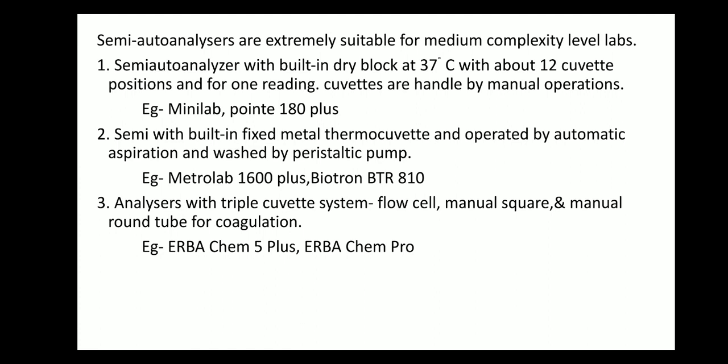So the aspiration, after the reagent and sample is mixed, once the reaction is over, to give out the reading, this mixture has to be aspirated, right? So that aspiration is automatic in this type. And washing is the washing of the flow pump and the cuvettes, which have to be rinsed and washed properly after each test, because to obtain accurate values there should not be any interference. That is also done by a peristaltic pump. Examples for this type are Metrolab 1600 Plus, Biotron BTR 810, all these.